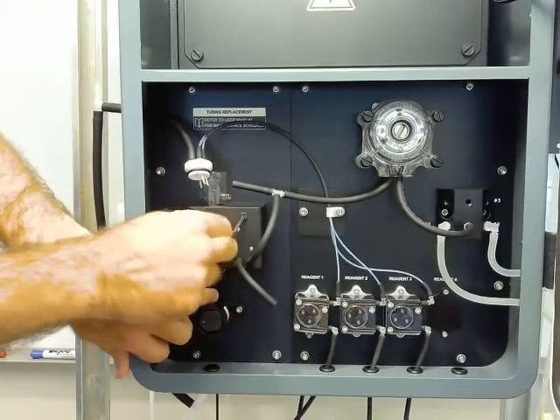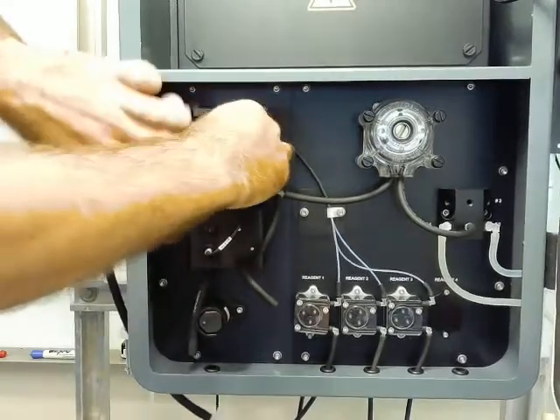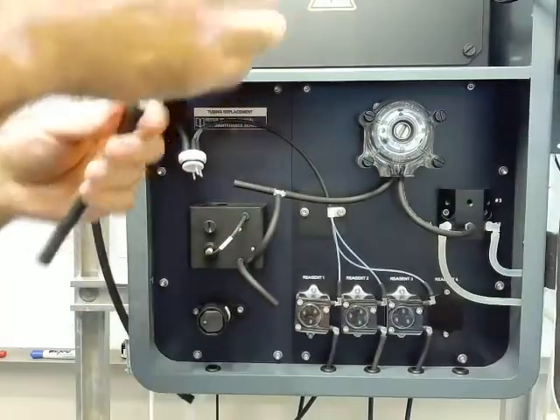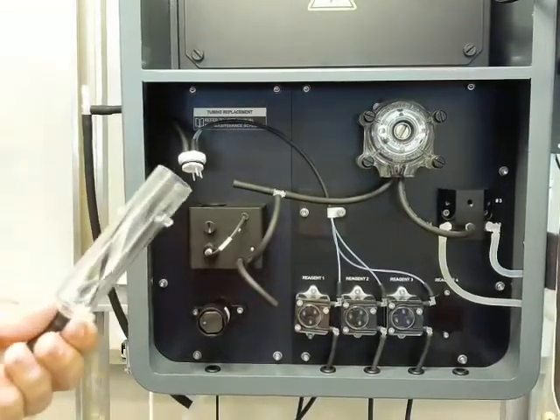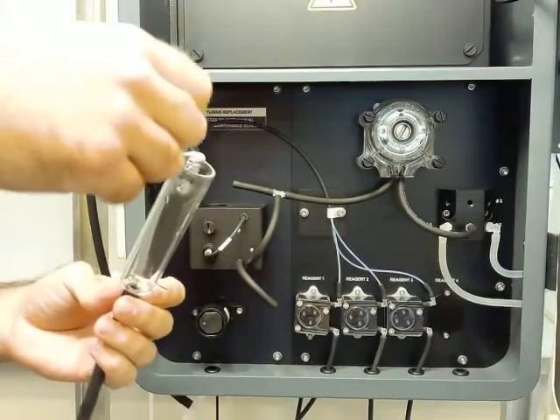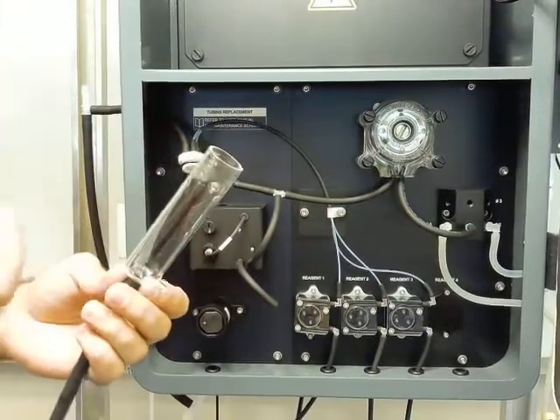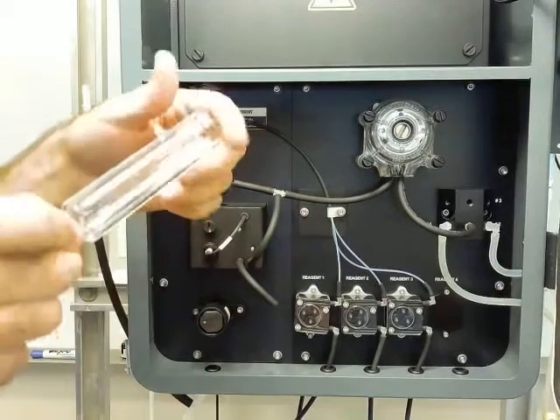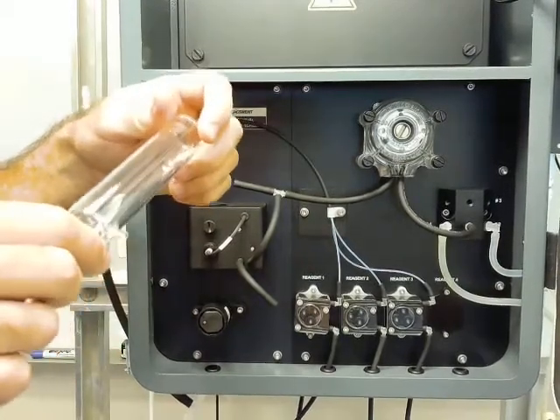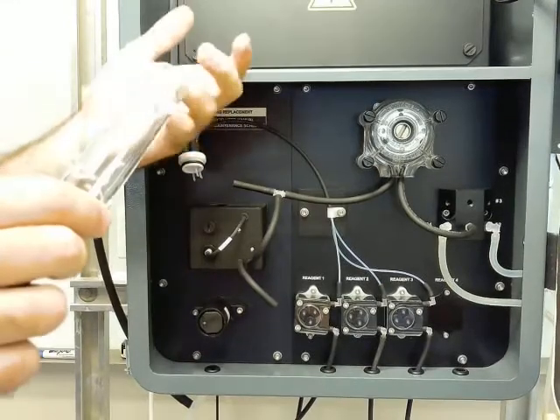We can undo this little thumb screw that just holds our flow cell in place, rotate it, and pull it out. So again, now that we have the flow cell out, clean it with a cotton swab, Kim wipe, no-lint paper towel. Obviously, we don't want to scratch this. Fingerprints will definitely throw off our readings. And again, if there's any buildup on the inside, we can certainly wipe that off.